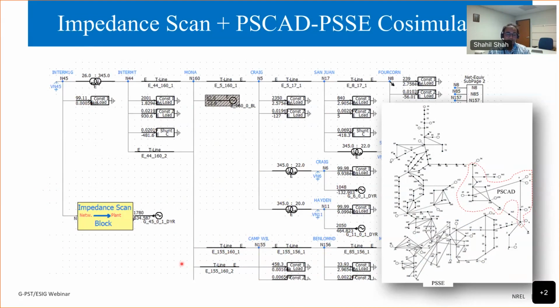The other scalability is that the tool can work with a big system simulated in an EMT simulation platform, or it can also work with co-simulation. Here I'm showing this tool residing in the PSCAD part of the system, but then this PSCAD part of the system interfaces with the PSSE network. So we can combine PSCAD, PSSE co-simulation, or EMT and phasor co-simulation, with the impedance scan tool to really understand the stability.